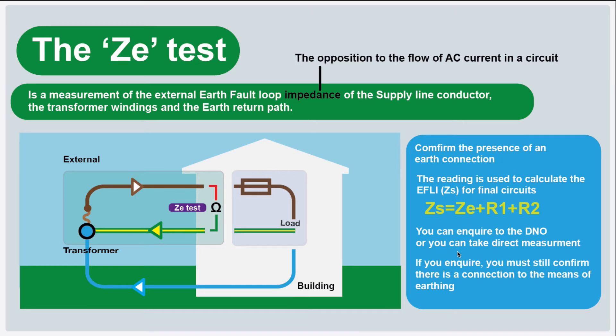This is an important test because it confirms the presence of an earth connection. It's also used further down the line in your ZS tests — when you're testing the installation internally, we need the ZE reading to get the ZS. You could inquire to the DNO about the ZE reading, but they'll just give you the maximum reading, or say they don't know. And even if you do inquire, you've still got to verify that you have an earth return path, so it's a test that needs to be done.